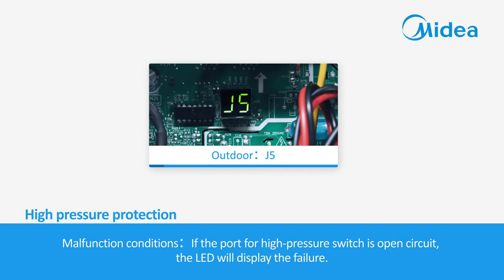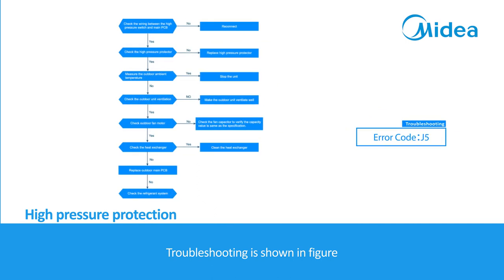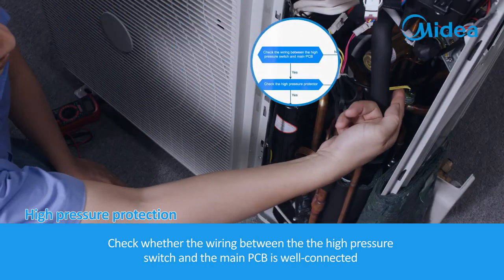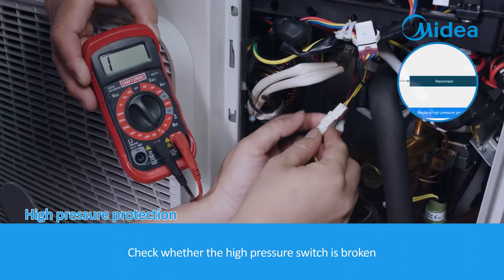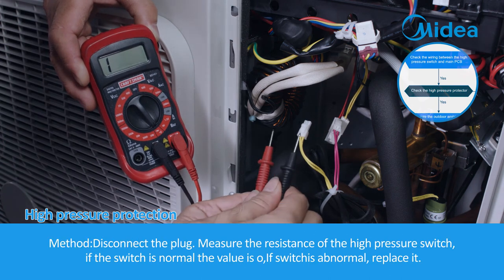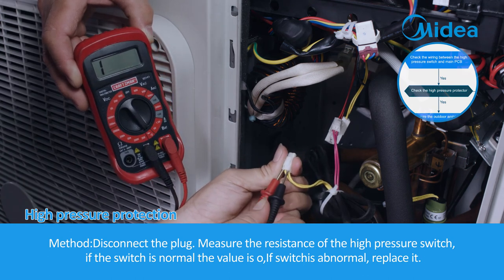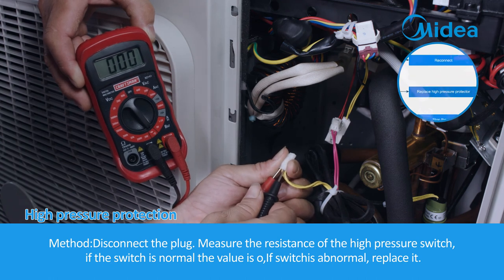High pressure protection. Malfunction conditions: if the port for the high pressure switch is open circuit, the LED will display the failure. The failure may be caused by wiring mistake, faulty high pressure switch, faulty outdoor fan assembly (AC motor only), system leakage or blocking, or faulty outdoor PCB. Troubleshooting: check whether the wiring between the high pressure switch and the main PCB is well connected. Check whether the high pressure switch is broken: disconnect the plug and measure its resistance. If normal, the value is zero; if abnormal, replace it.